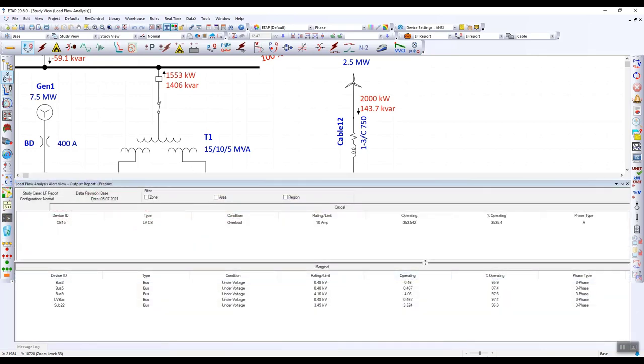At the bottom, we see our critical and marginal alerts. For our critical alerts, we see that circuit breaker 15 was overloaded with a rating limit of 10 amps and operating at 3,535%. We will definitely need to resize this breaker. Below that, you will see our marginal results. It looks like all of our buses were running at an undervoltage condition.